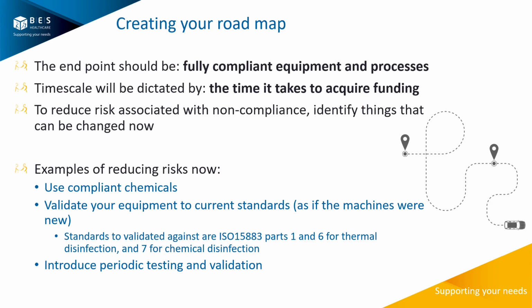So the standards that are relevant for this are ISO 15883 Part 1, and if you're using thermal disinfection, Part 6, and if you're using chemical disinfection, Part 7. So those standards dictate what those machines need to do and the testing required for those machines.